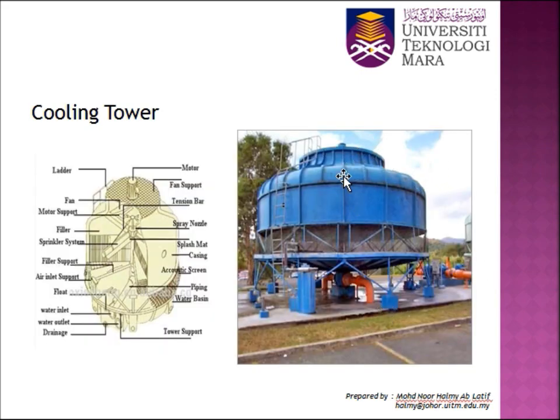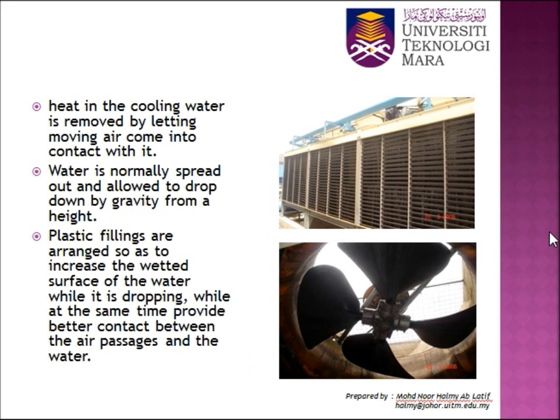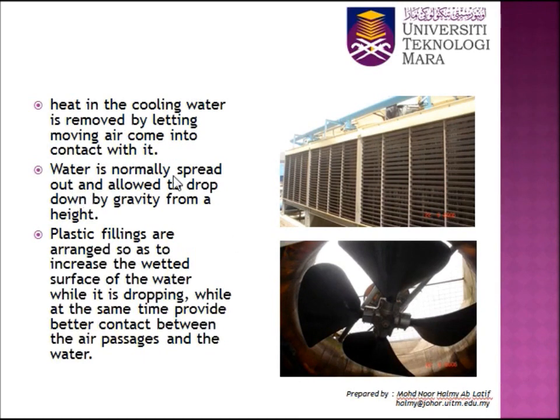Okay, so here is the example of cooling tower. Okay, pernah nampak tak? Pernah perasan tak? Pernah tengok? Okay, selalunya dia berada di luar bangunan. Selalunya dia berada di atas tanah. But sometimes dia ada di level yang paling atas dalam satu bangunan tu. Okay. So, heat in the cooling water is removed by letting moving air contact with it. Water is normally spread out and allowed to drop down by gravity from a height. Plastic fillings are arranged so as to increase the wetted surface of the water while it is dropping, while at the same time providing better contact between the air passage and the water.